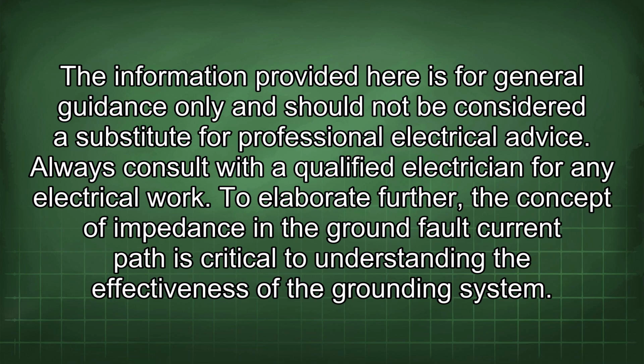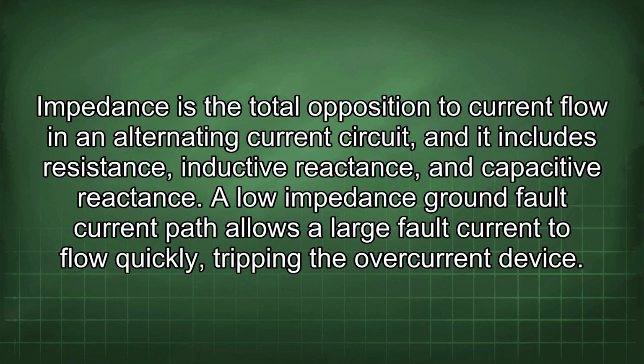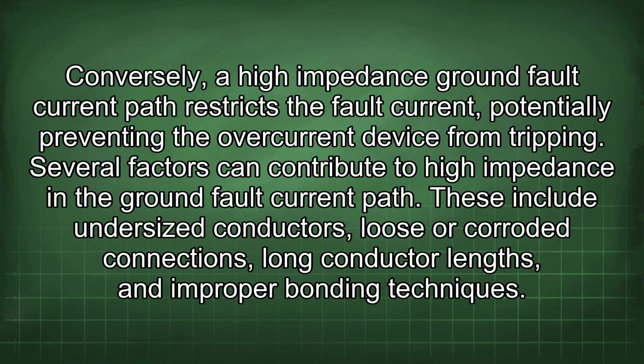To elaborate further, the concept of impedance in the ground fault current path is critical to understanding the effectiveness of the grounding system. Impedance is the total opposition to current flow in an alternating current circuit, and it includes resistance, inductive reactance, and capacitive reactance. A low impedance ground fault current path allows a large fault current to flow quickly, tripping the overcurrent device. Conversely, a high impedance ground fault current path restricts the fault current, potentially preventing the overcurrent device from tripping.